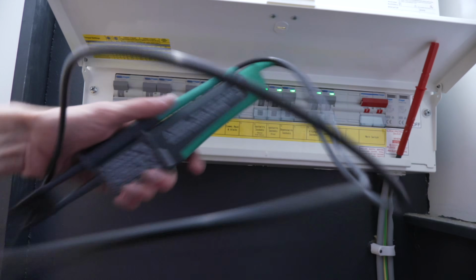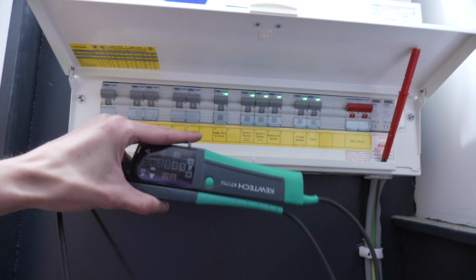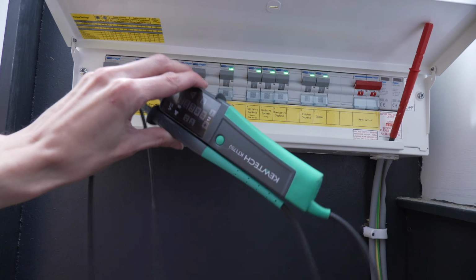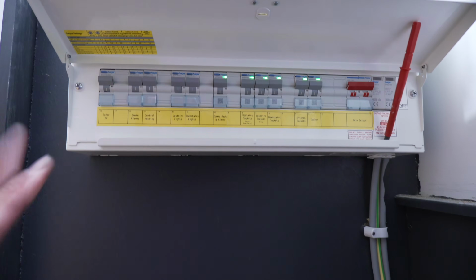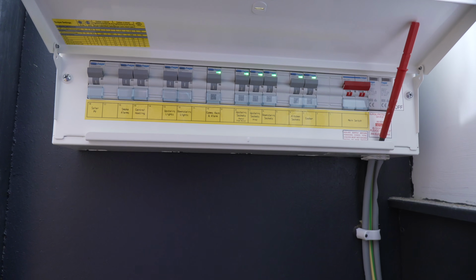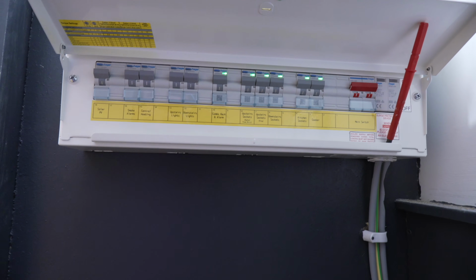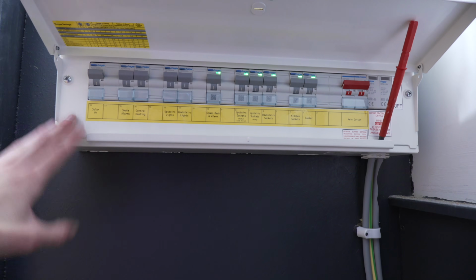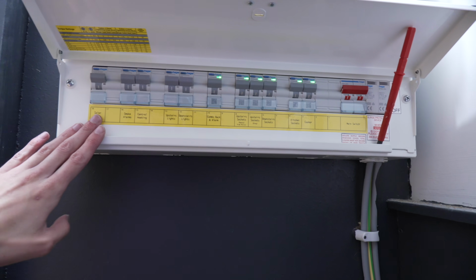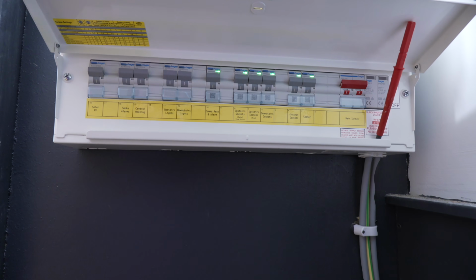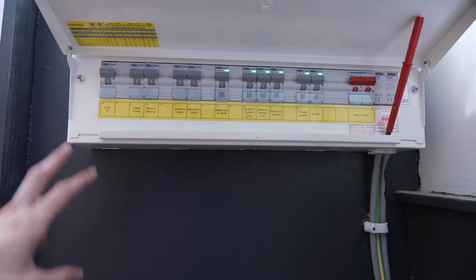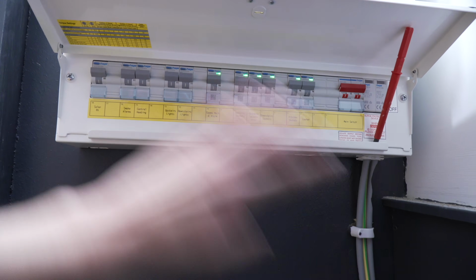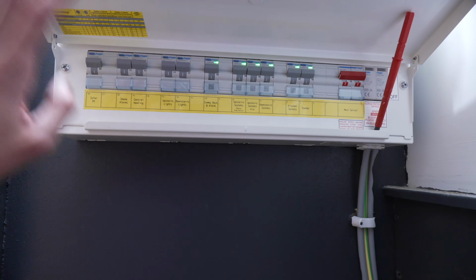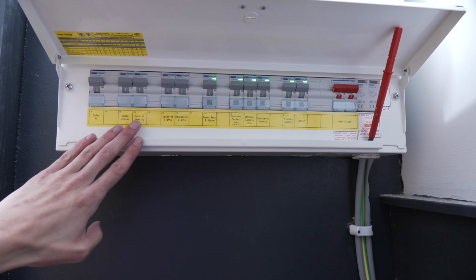What I'm going to be doing is making sure I safely isolate the consumer unit using proper equipment to do that. Don't just turn it off and hope it's off. Make sure you've got the proper equipment to safely isolate. If you have any doubt in how to do safe isolation, make sure you know how to do it or consult an electrician. For all these sorts of things like safe isolation, I'd strongly recommend checking out the GSH Electrical YouTube channel, who have loads of detail and proper training on how to do this sort of stuff. So we're going to safely isolate the consumer unit, get everything turned off, locked off and isolated, and then we can install those CTs.